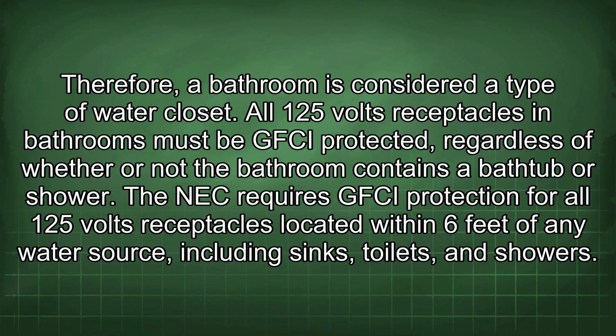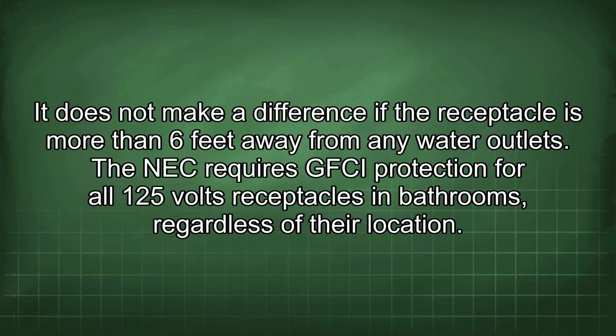All 125 volts receptacles in bathrooms must be GFCI protected, regardless of whether or not the bathroom contains a bathtub or shower. The NEC requires GFCI protection for all 125 volts receptacles located within 6 feet of any water source, including sinks, toilets, and showers. It does not make a difference if the receptacle is more than 6 feet away from any water outlets. The NEC requires GFCI protection for all 125 volts receptacles in bathrooms, regardless of their location.